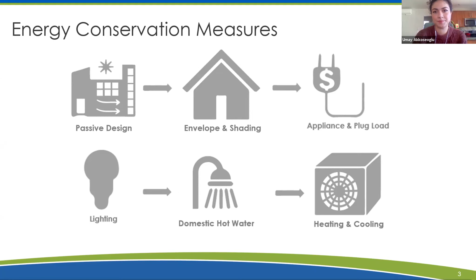Breaking down the energy conservation measures we implemented: ECM1 addressed building thermal performance. We improved thermal insulation by increasing wall insulation to rock wool insulation for the cavity, with an additional 2-inch exterior rigid insulation, bringing the assembly R-value of the walls to 21. We also added exterior board insulation to the roof, resulting in an assembly R-value of 50. For ECM2, we upgraded to high-performing triple pane glazing with a total assembly U-value of 0.2 and a solar heat gain coefficient of 0.23.